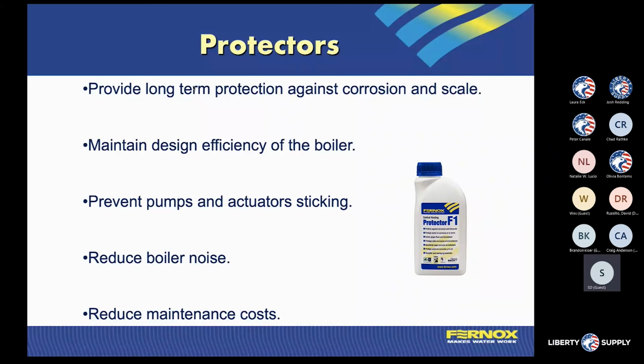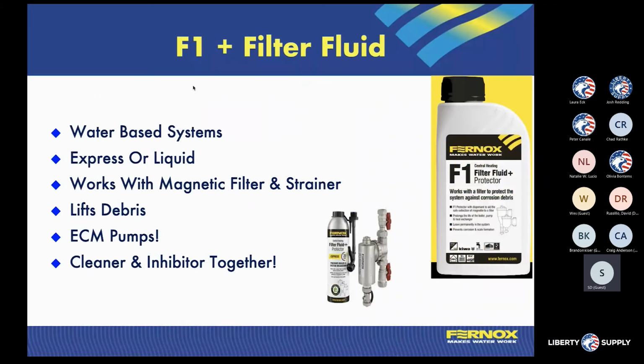It's still going to have some efficiency problems, but it's going to stop it in its tracks from getting further damage from that standpoint. So for the jobs where we can't flush and clean the systems, for a variety of different reasons, we developed a product that works with magnetic filters, and we'll talk about magnetic filters in a little bit. This is essentially our F1 that we just talked about, but we also add a detergent cleaner in there as a part of that process.